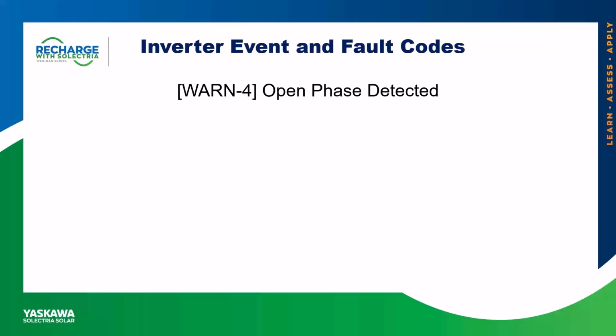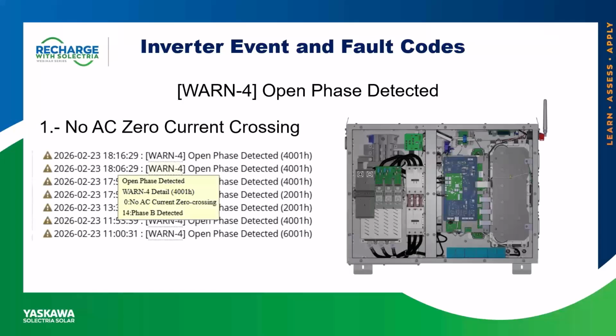Okay. Another fault you guys may encounter is WARN-4 Open Phase Detected. Specifically, this code can mean different things depending on the hex value it's giving you in the event and fault log. Right now, we're going to be focusing on no AC, zero current crossing. A quick tip, when you're troubleshooting the XGI inverter, if it's in a fault state, if you go to the event and fault logs and you hover over the fault code, this will give you further or more detailed information to what is going on with your unit.